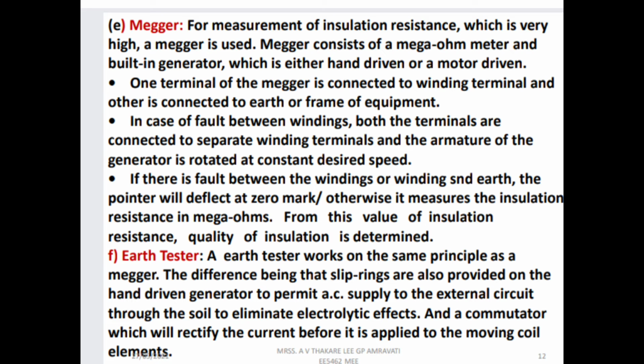Next is the earth tester. An earth tester works on the same principle as a megger. The difference being that slip rings are also provided on the hand-driven generator to permit AC supply to the external circuit through the soil to eliminate electrolytic effect, and a commutator which will rectify the current before it is applied to the moving coil elements.